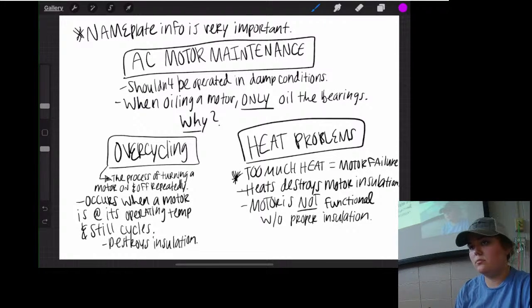A lot of them, when they overcycle, don't even get time to cool off. That's what I'm saying — heat is bad in any form, shape, or fashion, in the mechanical world and the electrical world. Heat destroys stuff, or it's a loss any way you look at it. So heat problems — too much heat equals motor failure — it destroys motor insulation, and a motor isn't functional without proper insulation.